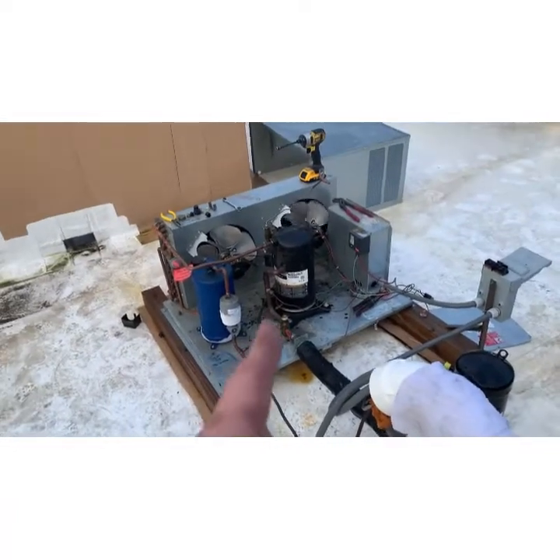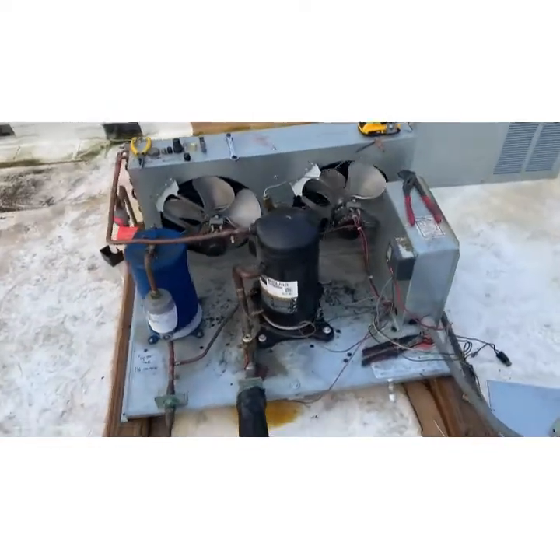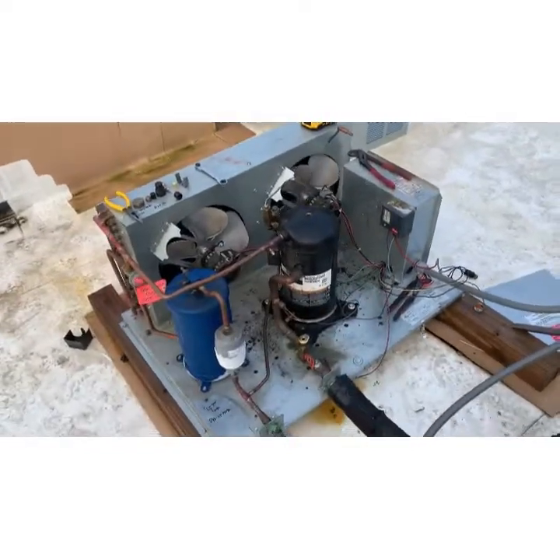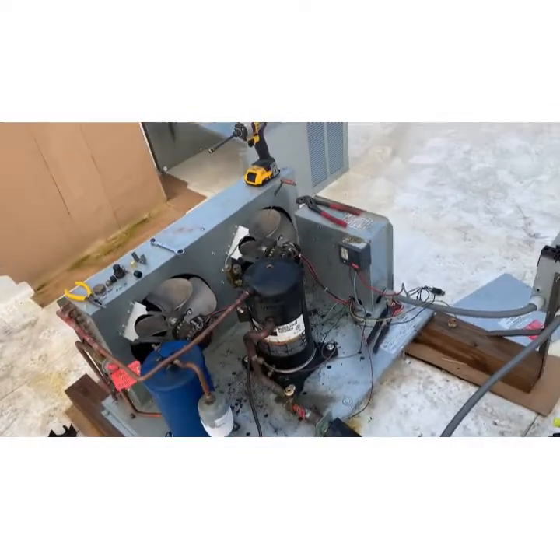Back again on a Master-Bilt cake freezer. The compressor is locked up — previous video showed locked rotor amps pulling 98 amps, won't start, obviously trips the breaker.